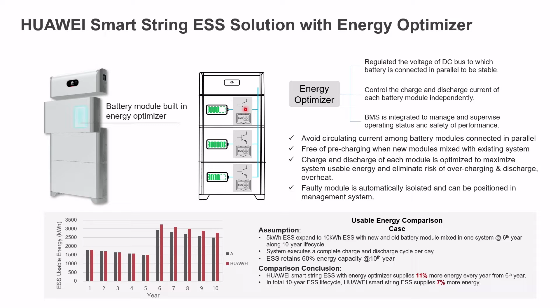Is there a special procedure if I want to add a new battery to an existing system? It's nothing special - you just physically connect it, put it into the modules. If you have the application to commission the system, you just log into the inverter and go through the commissioning process one more time, just adding the new battery. Only the first step is necessary, then the second step is detecting the new devices. All other steps can be skipped after that second step is done - we just wait for the battery to be discovered by the inverter. On Fusion Solar, the platform automatically adds the new devices.